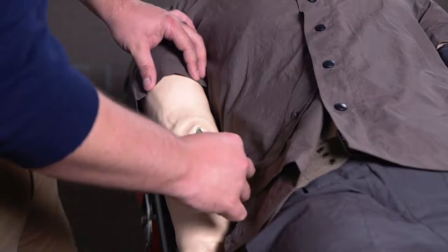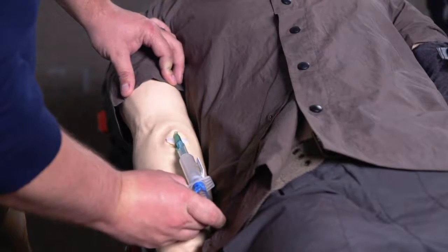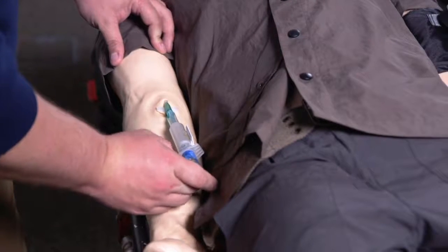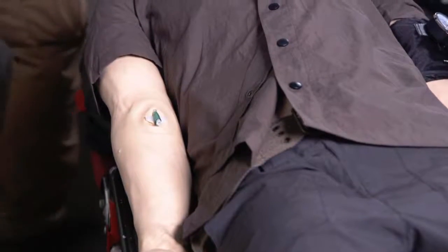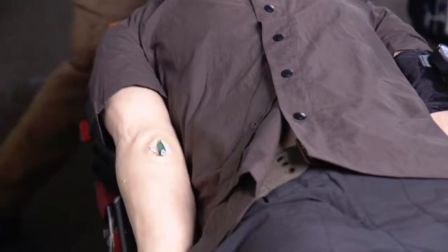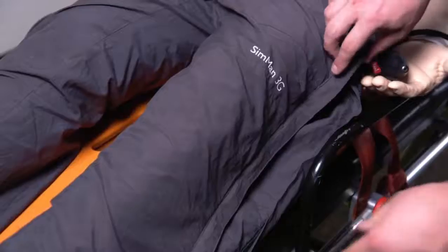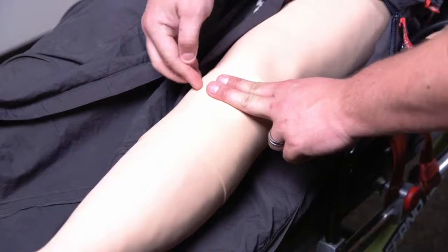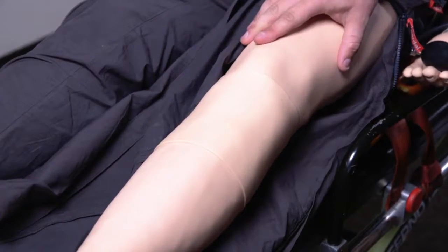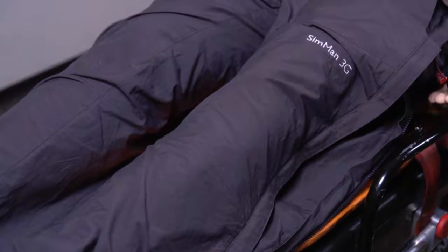The right arm already has an IV port in place with an RFID tag indicator, so that if you were to push any medication, it will read that medication and concentration based on the tag you are giving and the amount of fluids you give. You're also capable of hooking up any drip sets to that arm as well. Now, in some instances where we're unable to establish an IV, Sim Man is capable of getting an IO into his left leg. You'll be able to palpate the correct location, drill into his leg, start an IO, and run fluid through there as well. Unfortunately, no medication through the IO, as there's no RFID tag reader in that location.